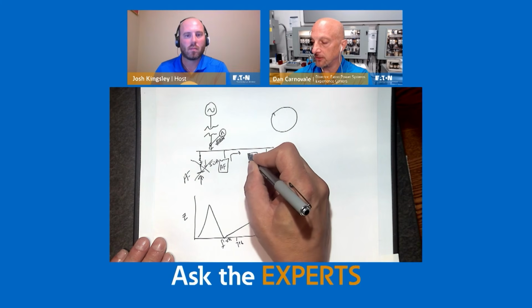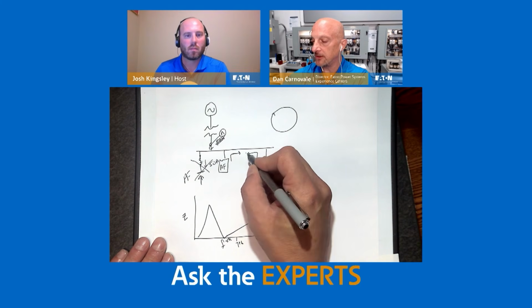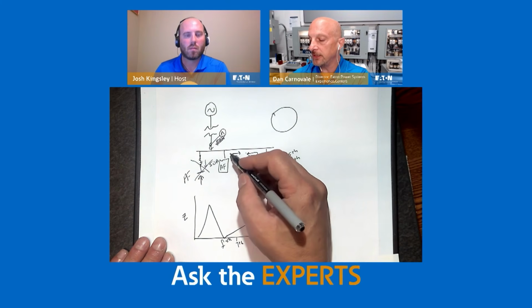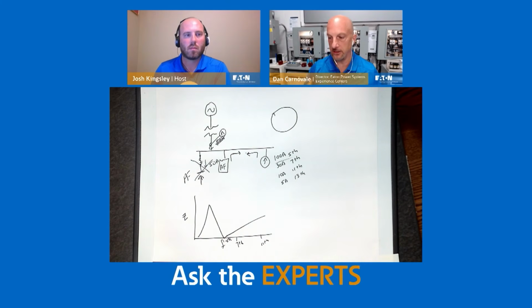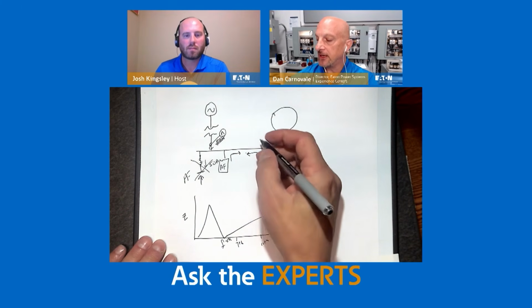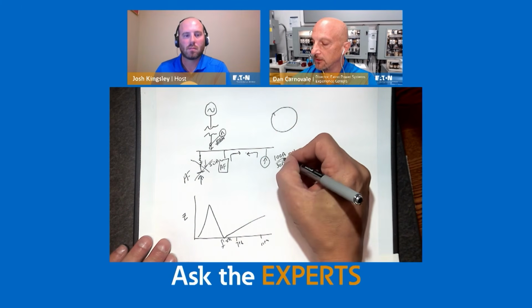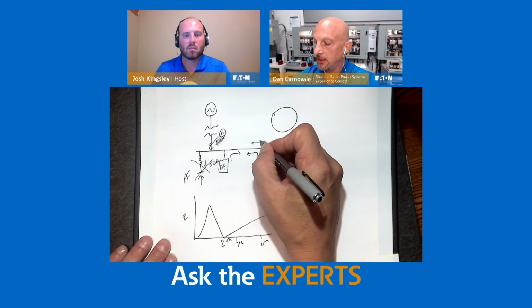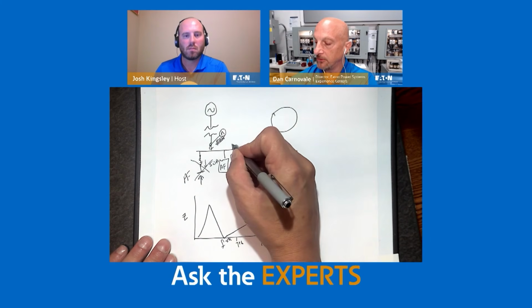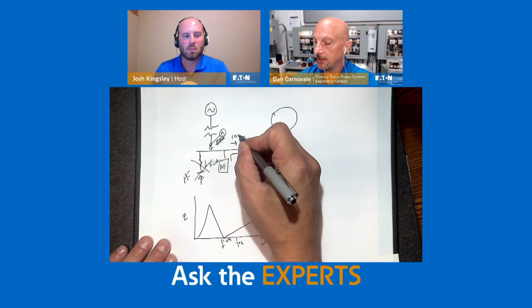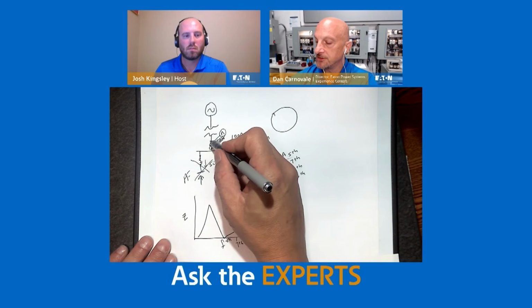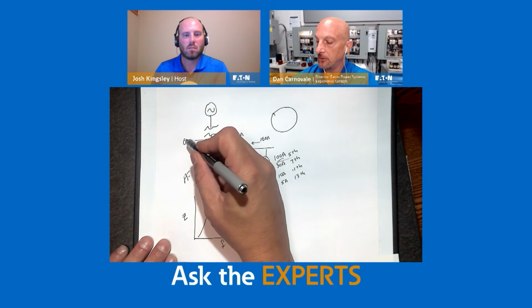So if current is flowing this way and this way, say out on phase A, back on B and C, out on phase A, back on B and C. Where these two meet, again, it's like noise cancellation in my earphones or in your cell phone. It basically cancels it out. So this fifth harmonic here, if it's 100 amps going this way, it literally could put 100 amps going this way and cancel it out. And so what you see back here then is 0 amps.